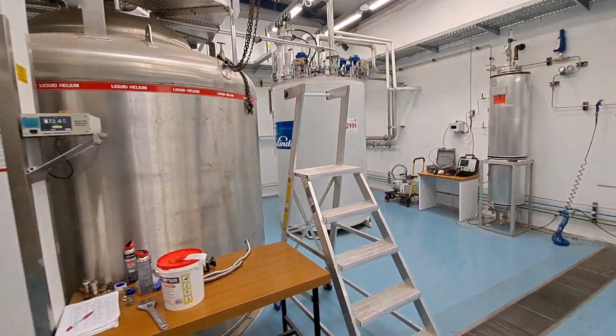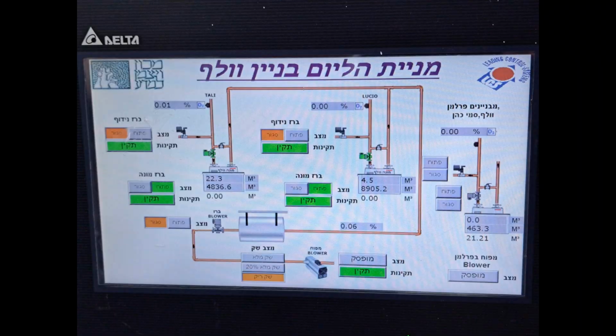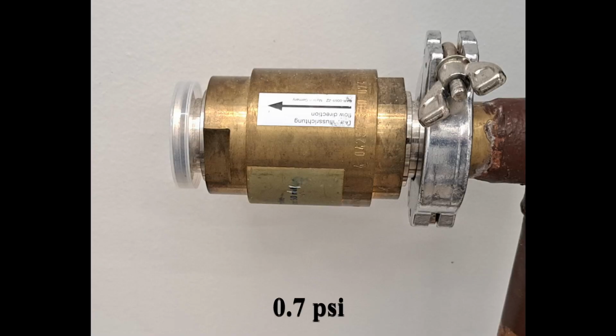the Hebrew University uses. Each installation is attached to a programmable logic controller, PLC, that monitors and controls the helium sent for recycling. On each line there is a check valve set to 50 millibar to prevent overpressure on the magnets. The check valve that we installed was cheap and may be leaking.